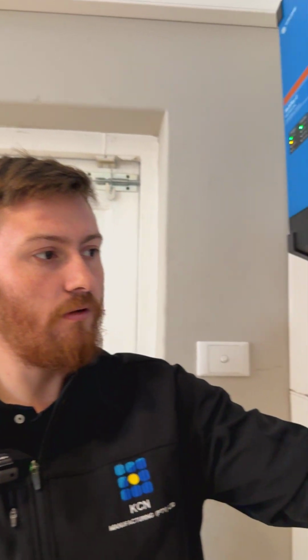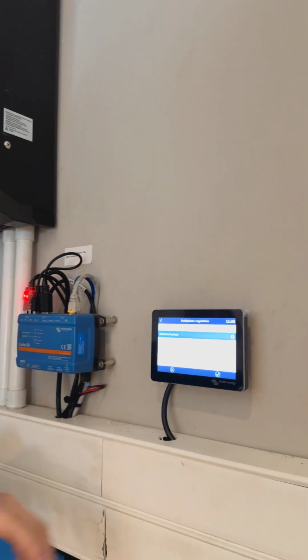If you use total of all phases, it will use the total of those 3 phases and make sure that stays at 0. So if you're pulling 3,000 watts on phase 1, but only 50 watts on phase 2, it's going to start pulling off of phase 2 and pushing back on phase 3 to keep the total value of all three phases as close as possible to 0.